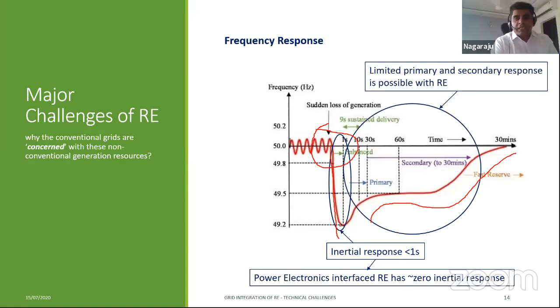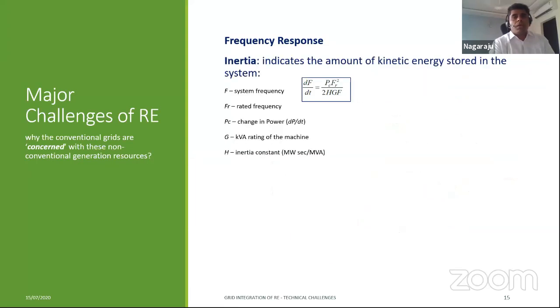And in terms of primary and secondary response, the renewable energy sources do have some limited capabilities, and they do help, but not to the same level as conventional machines. Okay, as I said, I'm just trying to give you a theoretical explanation. So inertia indicates the amount of kinetic energy stored in the system. Previously it is basically the rotating mass of the conventional machines. Now with renewables, we are not having that. Although wind turbines do have rotating mass, they are disconnected or decoupled from the grid. We cannot count that.